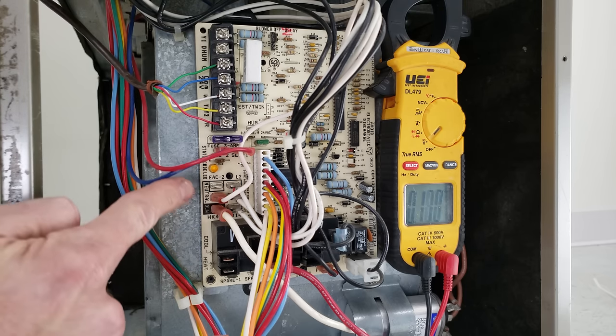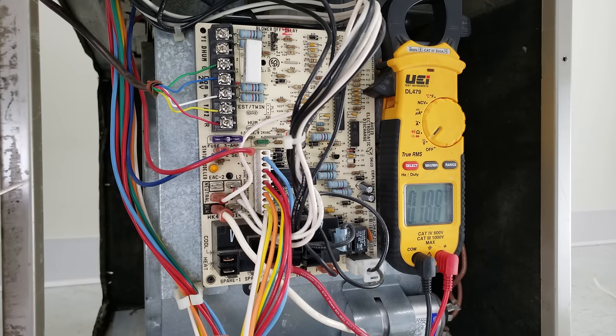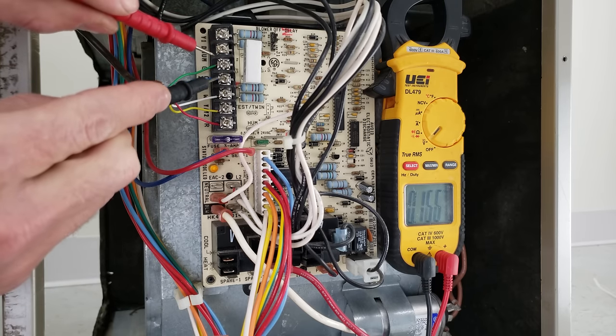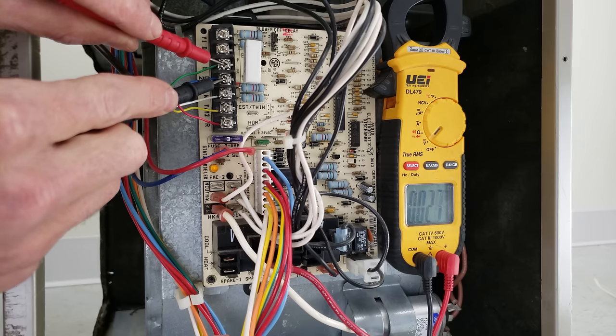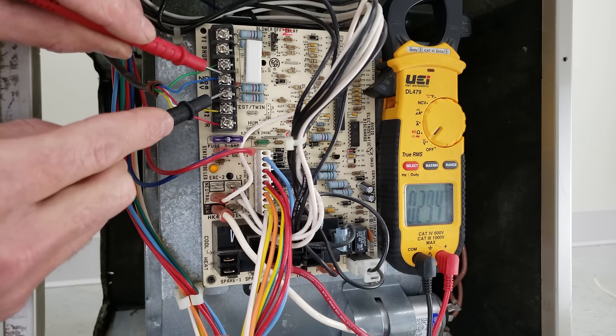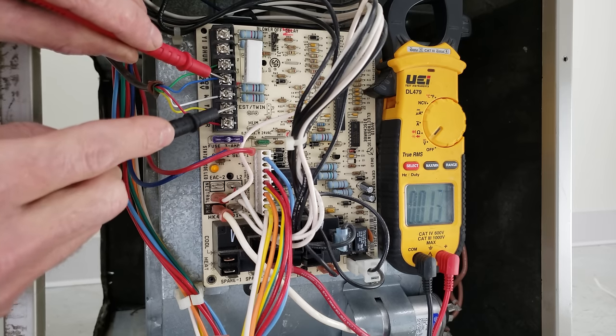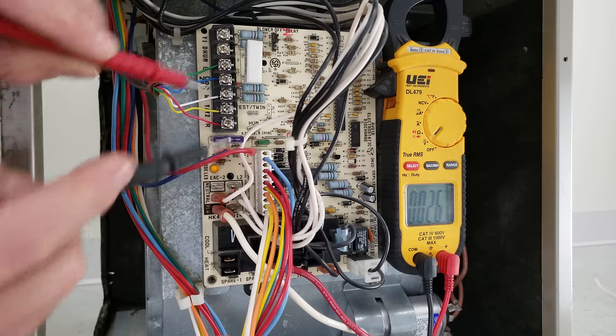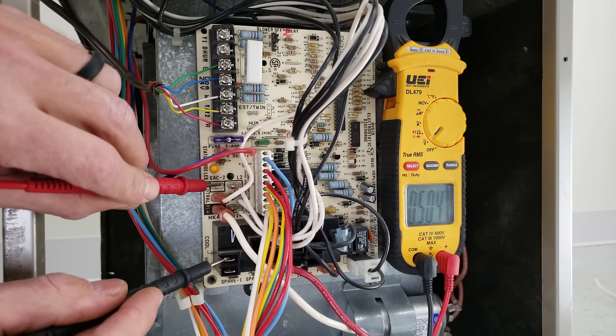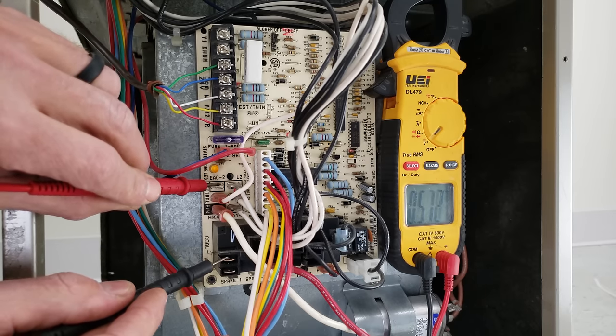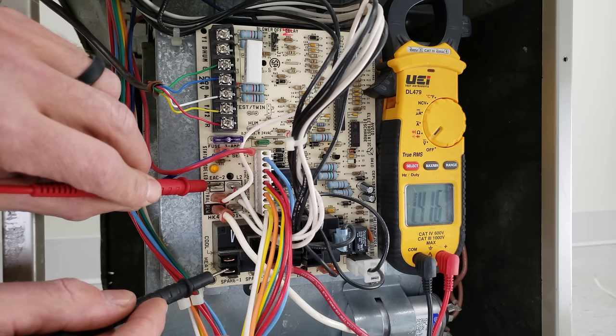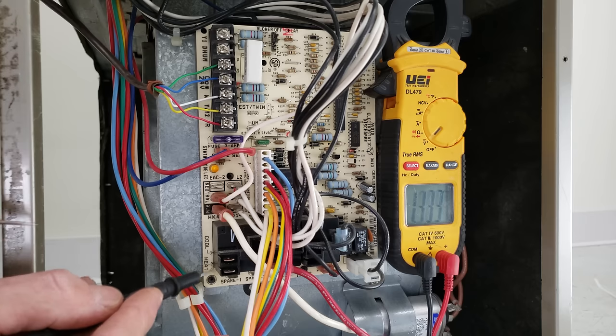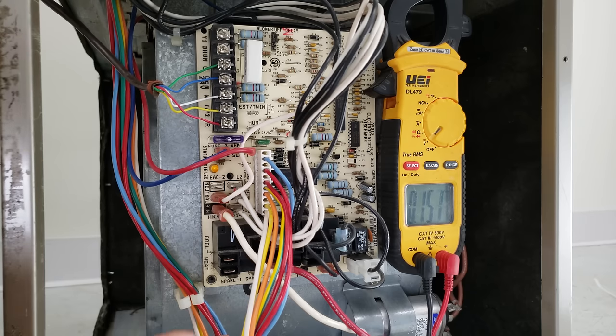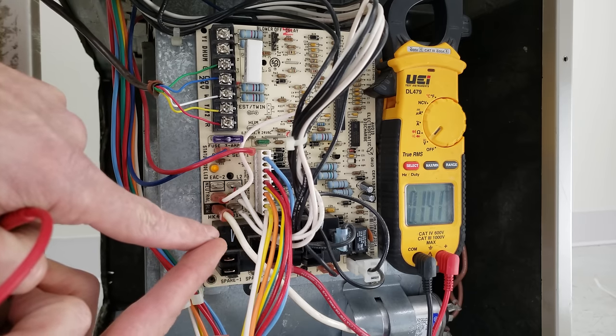And if you have a solid status code light and you have no power on the G terminal, so you have 0 volts there, and you have no power on the W or the Y, but you do have 120 volts down here on this relay, on this contact, then you know that inside this box, that relay, basically the contacts are welded together.